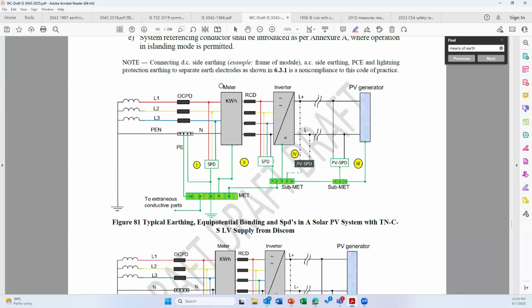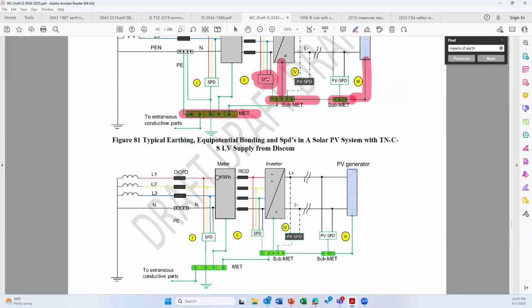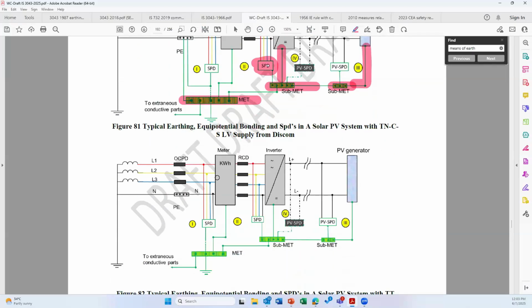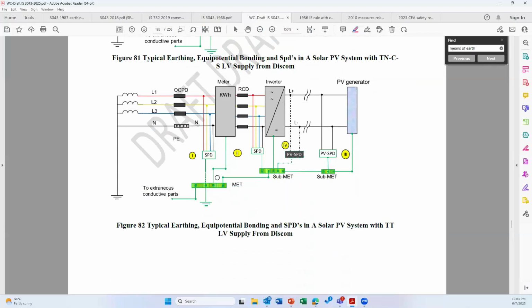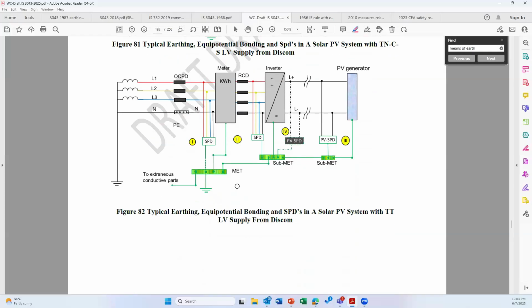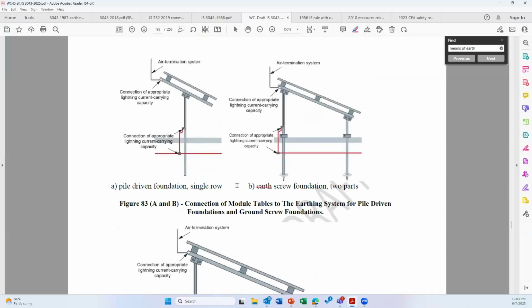This figure is again from an IS standard, which tells you, as you can see here, there is a common earth bus bar. So all the metallic parts, exposed and extraneous conductive parts, are connected to the common earth bus bar. This also explains where to use the SPD and so on. Two types of connections are shown. One is for a TN-C-S system, and the next one is for a TT system. So both the figures are included. The system remains the same. Every metal part is connected to a common bus bar.